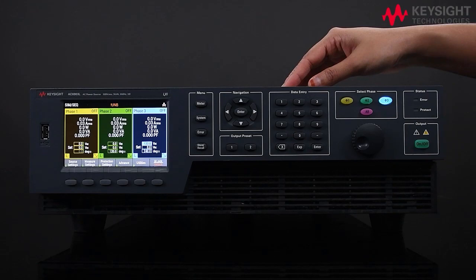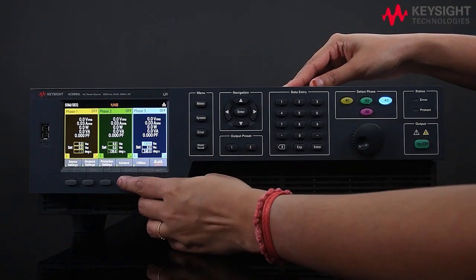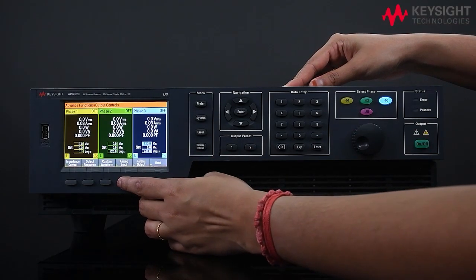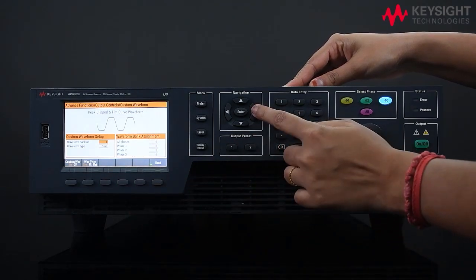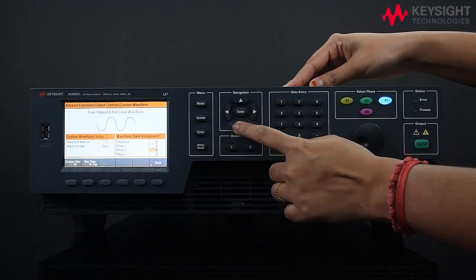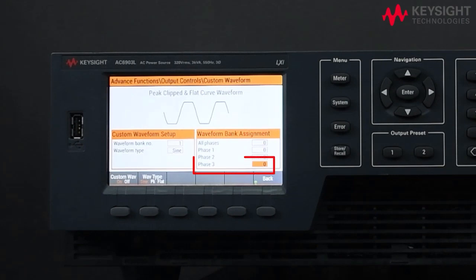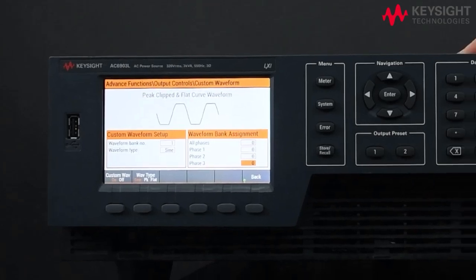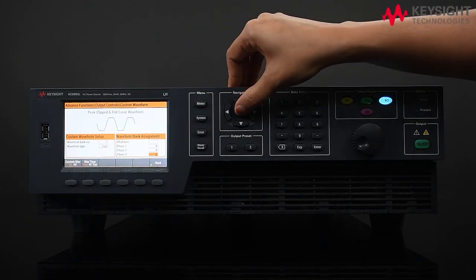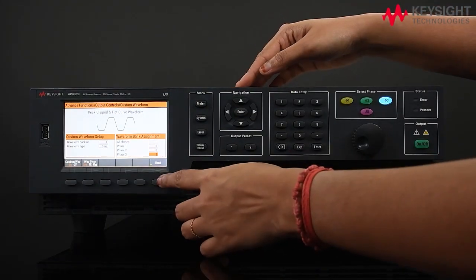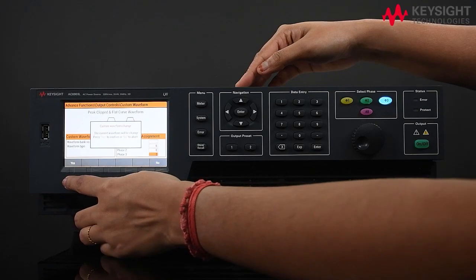Next, we need to configure the custom waveform settings. Press Advanced Output Control, then Custom Waveform. Choose the phase that you wish to load the waveform to, for example phase 3. Make sure the output of phase 3 is connected to the power analyzer in order to view the waveform. Earlier in segment 1, we set the custom waveform on waveform bank 2, so let's set waveform bank 2 to phase 3. Make sure to press Back and Yes to confirm the changes.